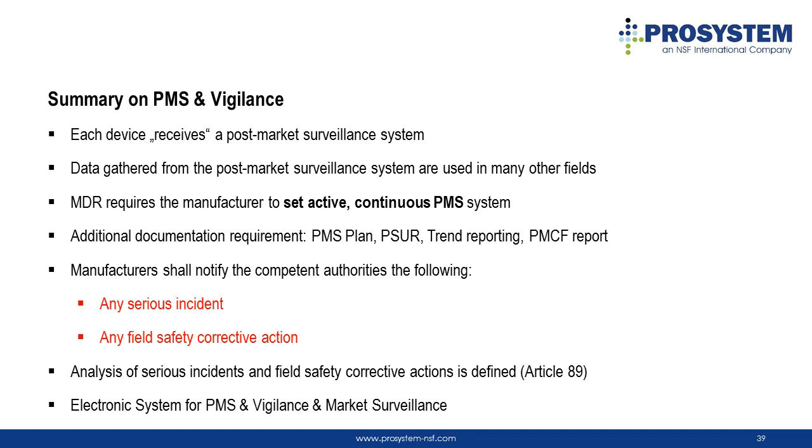Data should be gathered actively from the post-market surveillance system and used in many other fields, such as to update the clinical evaluation, the risk-benefit assessment, and to improve the product performance and safety. MDR requires the manufacturer to set an active, continuous PMS system. The PMS system interacts with other processes and technical documentation.